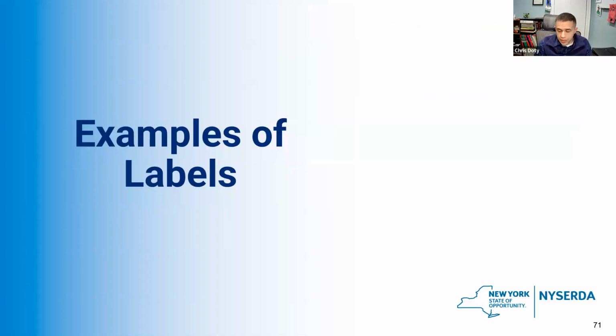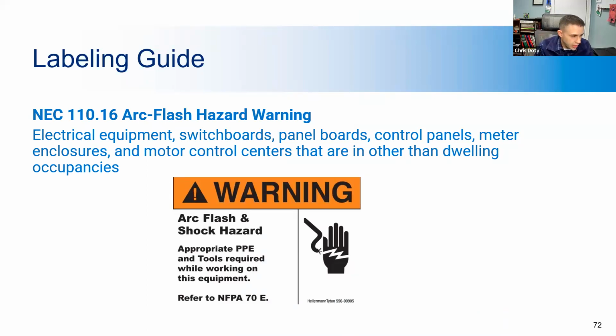So now we'll go through some of the labels that are required for solar projects. As I mentioned, all solar PV signage is yellow, orange, or red, so it's really easy to identify for electricians and code officials. First we have the arc flash warning. This is required on basically all electrical equipment, switchboards, panel boards, control boards, meter enclosures, and motor control centers that are in other than dwelling occupancies. These are super important because arc flash incidents can cause death, and if not, they can cause serious injury or blindness or different things. So it's super important.